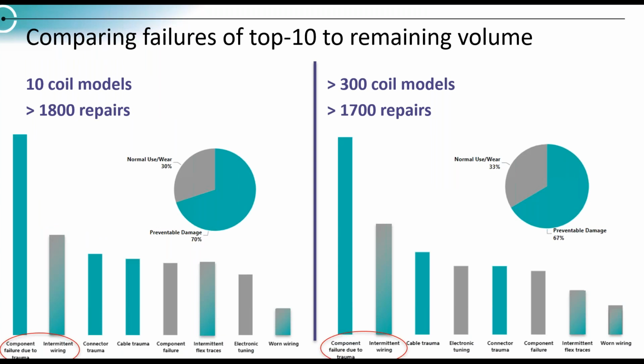So you might not have one of our top 10 coil models in your facility. Those top 10 coils comprised about half of the coil volume that we have done in the last 2 years. But there are well over 300 other coil models that we have worked on just in the last 18 to 24 months that have comprised about the same volume that our top 10 coil models have consumed. But if we compare the failure analysis data between our top 10 and the remaining 300 different coil models, if we would overlay those, you're going to see a definite pattern occurring. Component failure due to trauma and intermittent wiring. Connector and cable trauma are the next ones down out of that list. So you see a definite pattern with coil failures, whether you're in the top 10 or you're in the other 300 models.